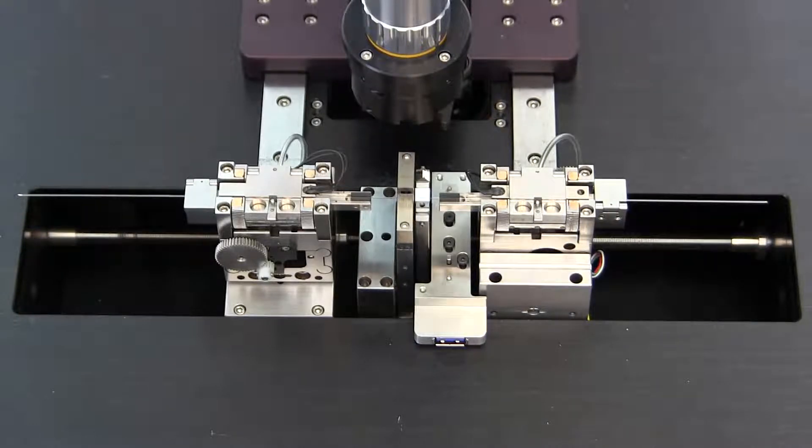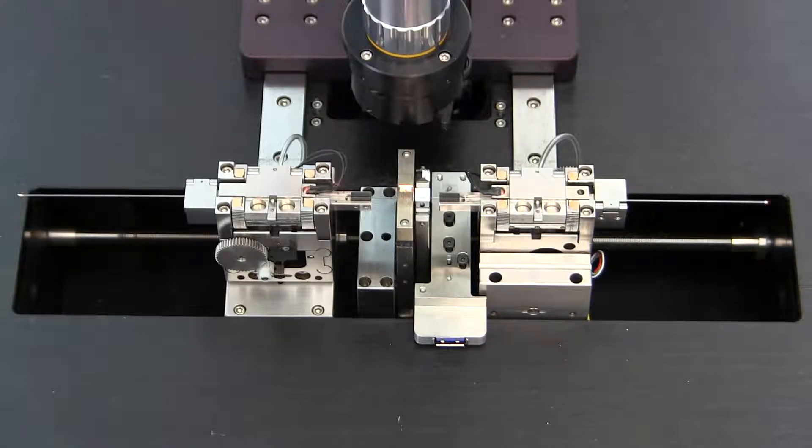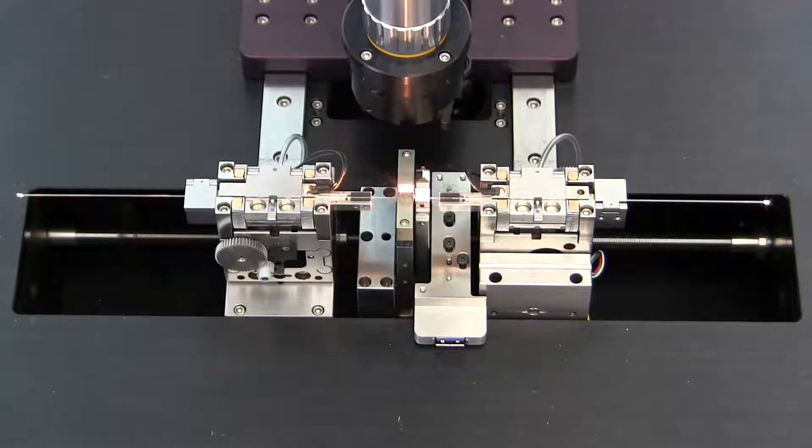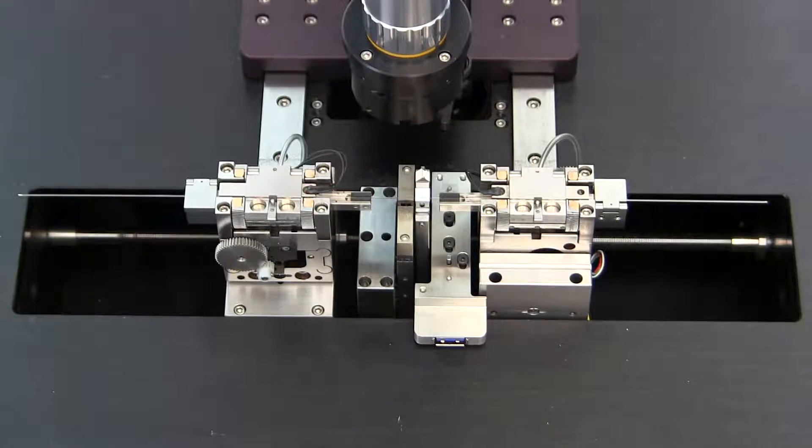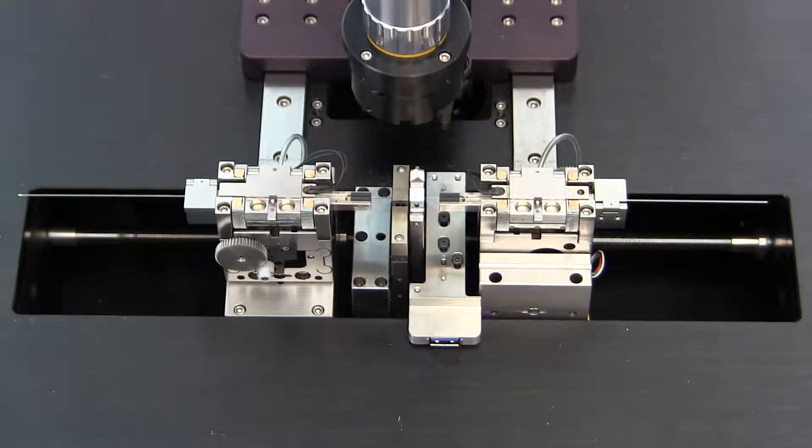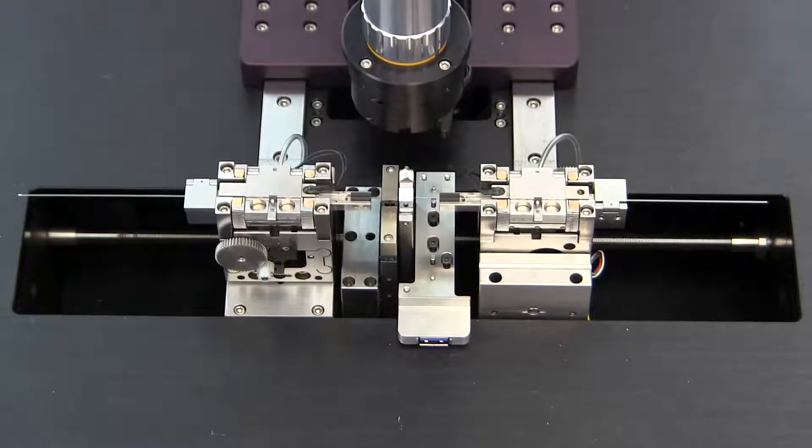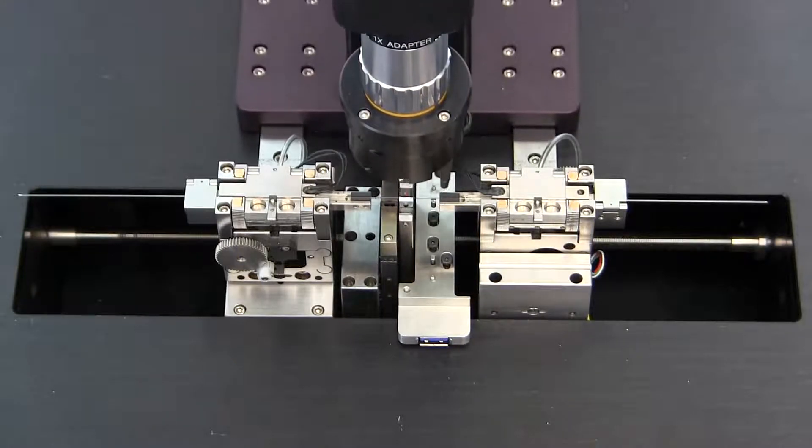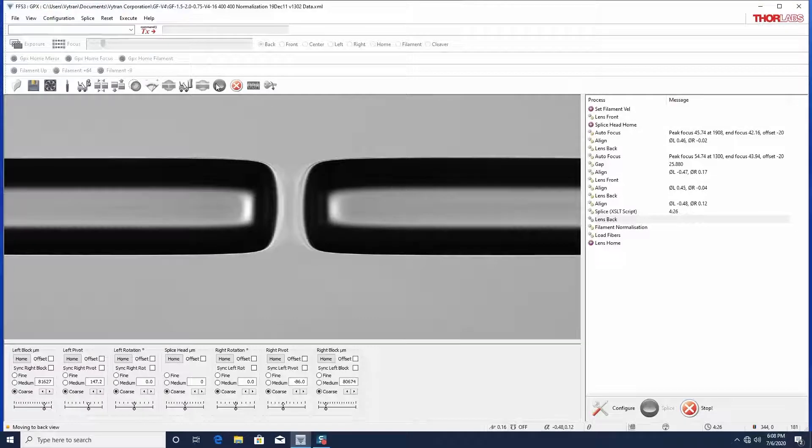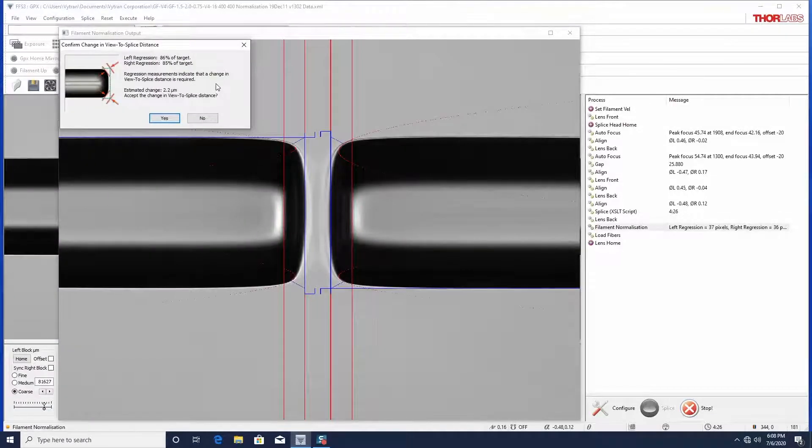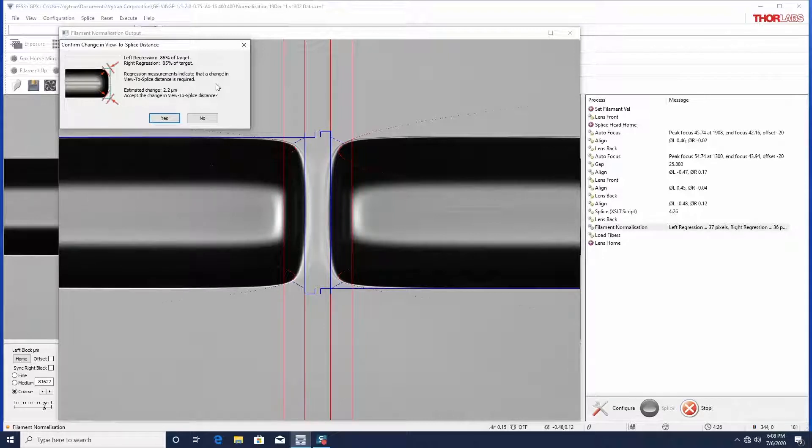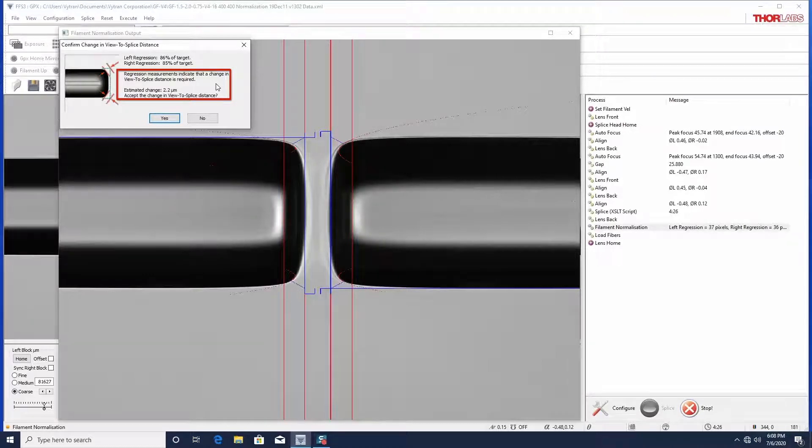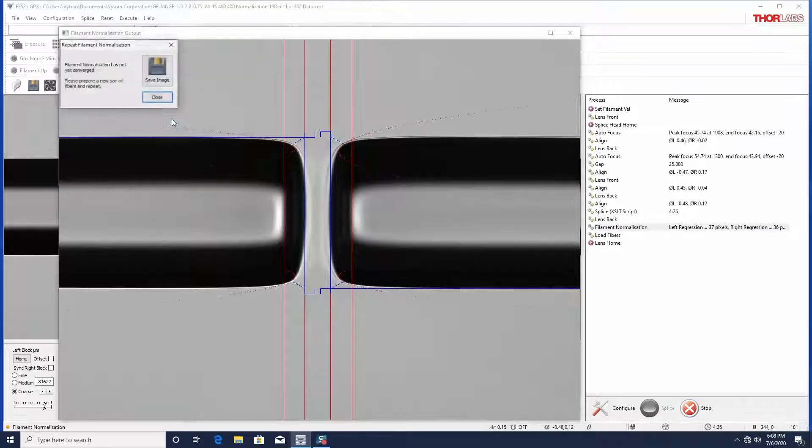The filament then applies a standard amount of heat to the fibers and the surface tension causes the ends to round. The software then analyzes the image and compares the amount of rounding to what is expected. Based on these measurements, the FFS3 software will recommend an adjustment to the view to splice distance and the filament power offset, so that the filament provides the required heating effect.